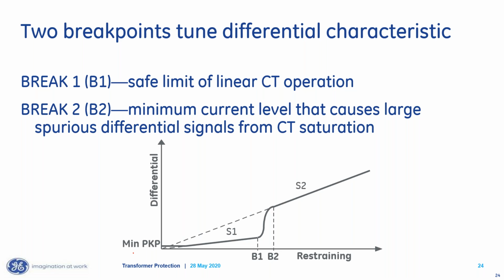You want to set that low slope region to take care of CT inaccuracies in the steady state, right? What that means is under sort of normal conditions. You want to set that upper region to take care of CT inaccuracies when you have a real heavy through fault, where you can have heavy CT saturation. So for that reason, you want to set your lower break point to be the point where you are within safe limits of the CT operating. So in other words, you're not going to saturate for a fully offset waveform. If you do that calculation, that's going to depend on the size of your CTs, your fault current, the accuracy class of your CTs. That quantity may be anywhere from 4 to 2.